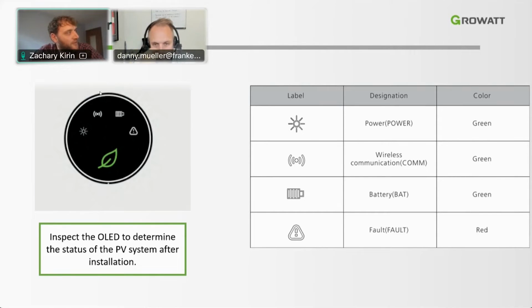If there are any faults in the system, the fault light will turn red. And this would be the most important LED to look at, in my opinion. So in normal operation, you'll see at least 2 of these be green. If you have a battery system, the battery will be green. And then no red should be on the fault LED.